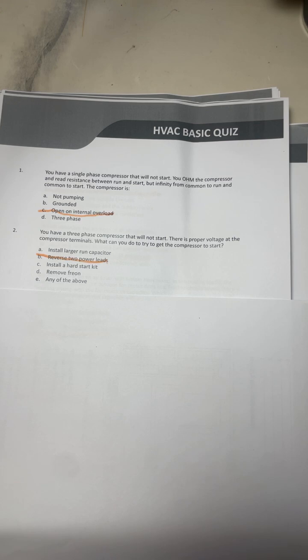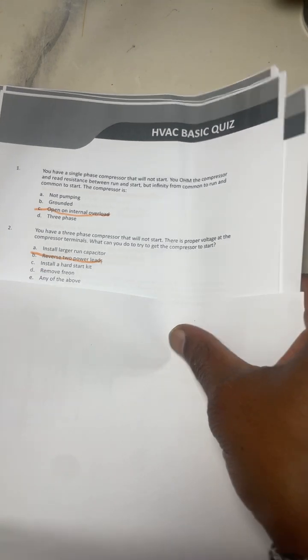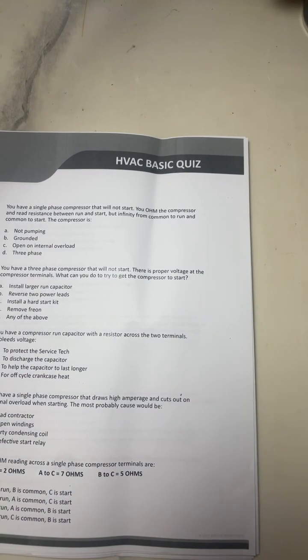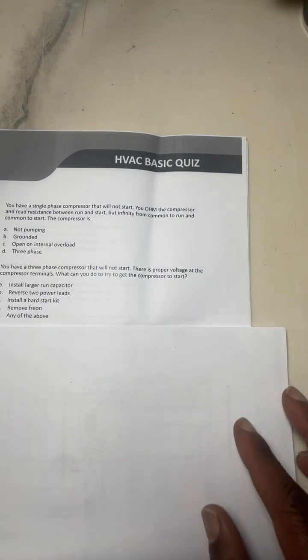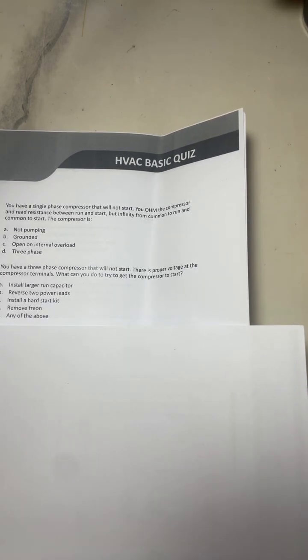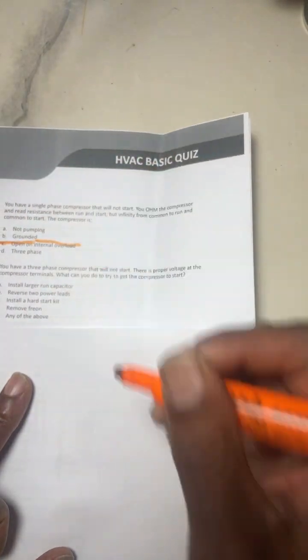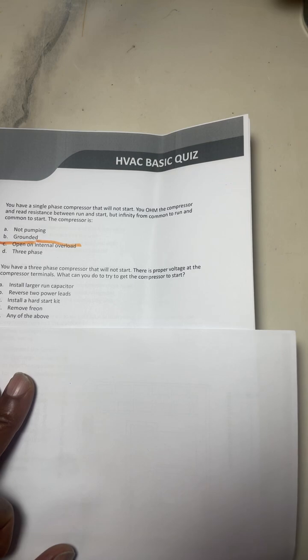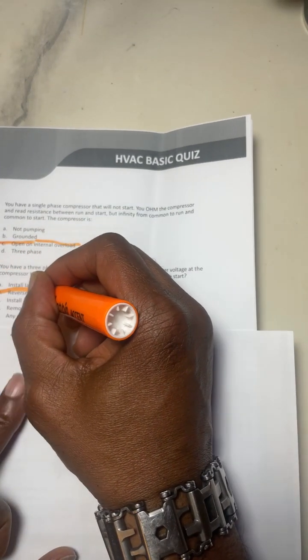You have a three-phase compressor that will not start. There's proper voltage at the compressor terminals. What can you do to try to get the compressor to start? You know what I'm gonna do? I'm gonna do it like this. I got a blank copy. So number 2. Number 1 is C. Number 2 is B. Reverse the 2 power leads.